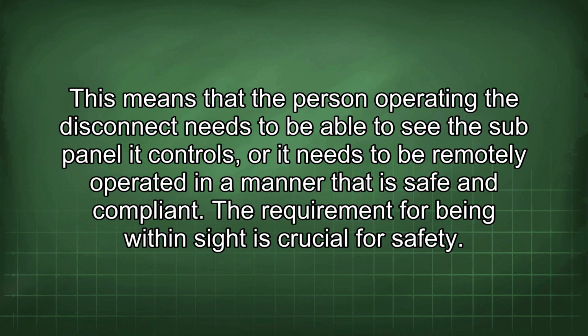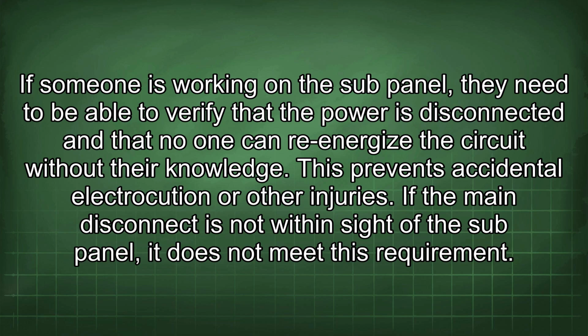The requirement for being within sight is crucial for safety. If someone is working on the sub-panel, they need to be able to verify that the power is disconnected and that no one can re-energize the circuit without their knowledge. This prevents accidental electrocution or other injuries. If the main disconnect is not within sight of the sub-panel, it does not meet this requirement.